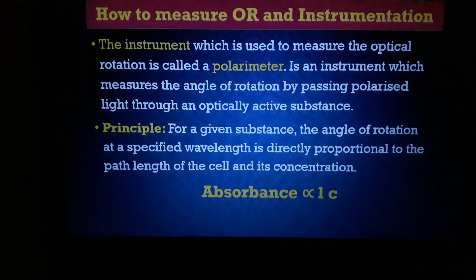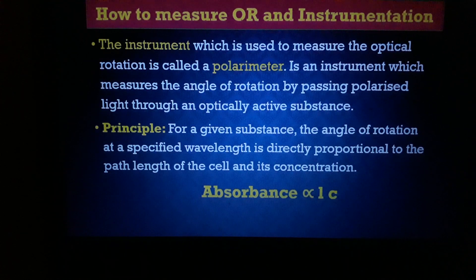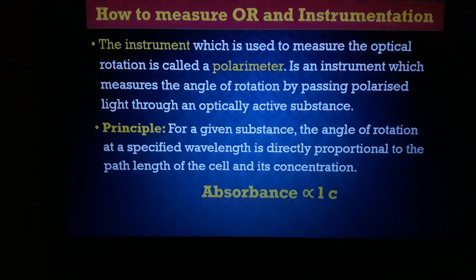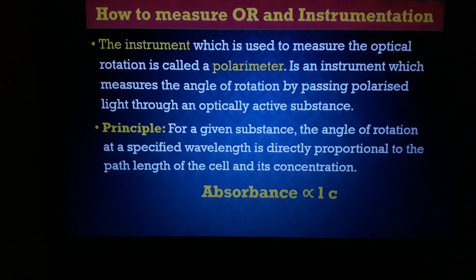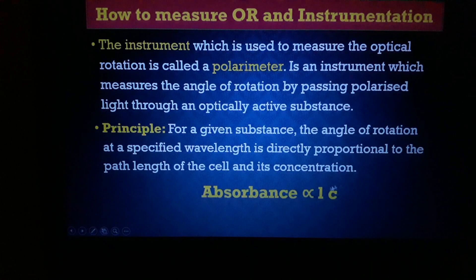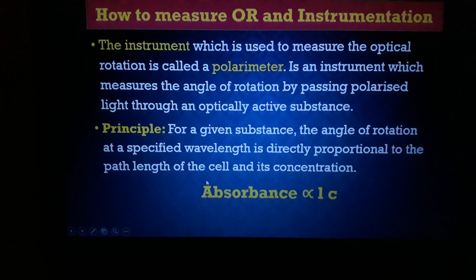The instrument used for measuring optical rotation is called a polarimeter. A polarimeter measures the angle of rotation by passing polarized light through an optically active substance in solution. The principle is that for a given substance at a specified wavelength, the angle of rotation is directly proportional to the path length of the cell and to the concentration of the solution.